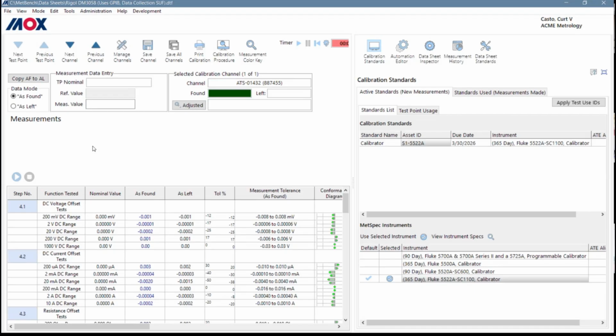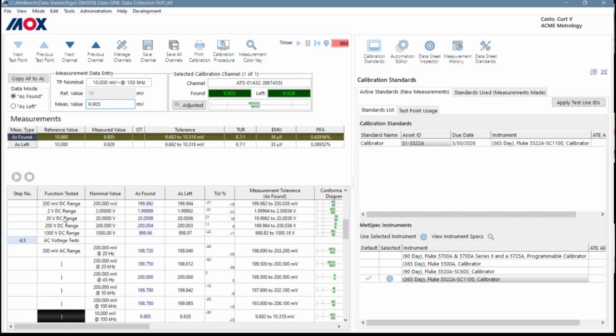Correct, or having it organized to where it's pulling in the ranges. I've seen some programs just have issues with recognizing that this is part of the uncertainty budget, or this is the spec for this portion of the calibration. So yeah, it knows what module, you have that CPC and it's multiple modules. It knows what module to pull from. It's pretty smart and intelligent that way. I agree.